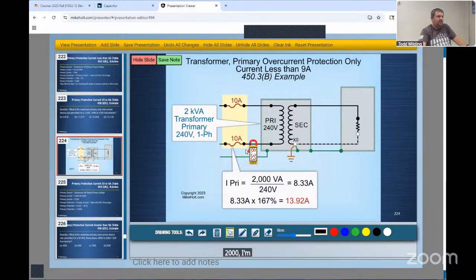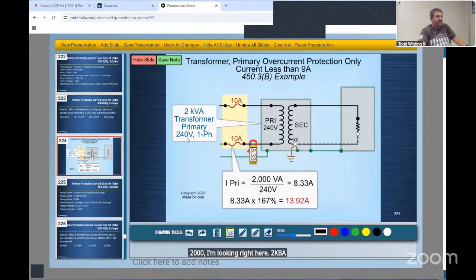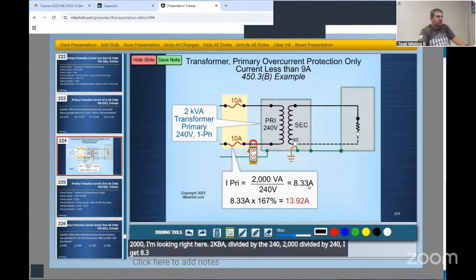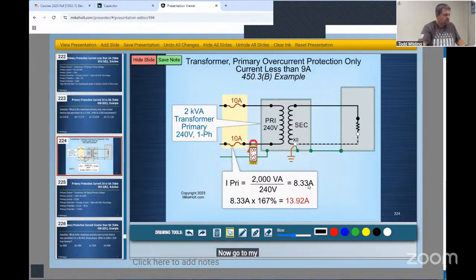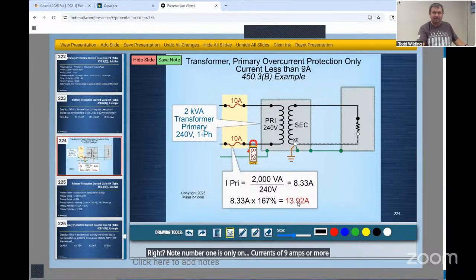2000, I'm looking right here. 2 kVA divided by the 240, 2000 divided by 240, I get 8.33. Now go to my table. Less than 9 amps, I multiply it by 167%, right? I get 13.92. Am I allowed to go up? No, I'm still not at 9 amps or more at 125%. Right? Note number 1 is only on currents of 9 amps or more and 125%.